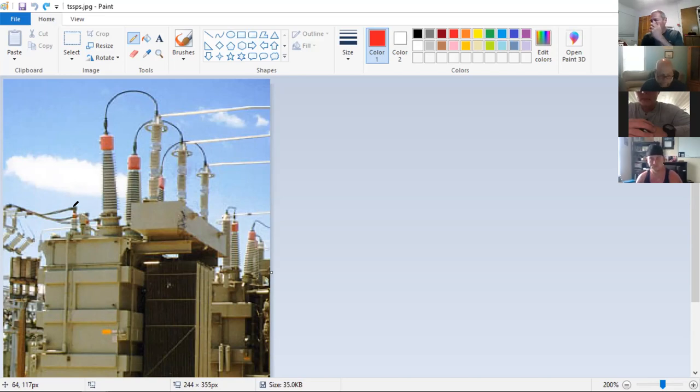So I know you guys have been out in the field and you've climbed up on those short poles to a couple cross arms and you've seen the insulator that's on those cross arms. That's designed for being used on a 7,200 volt system. The insulator itself usually is able to handle up to 20,000 volts. Now, you want some room for safety purposes. You don't want to put 20,000 volts on a 20,000 volt insulator because it gets dirty, contaminated, wet. You almost want to double the amount of protection that you have on your system as far as insulation is concerned. Any input on that, Robbie?